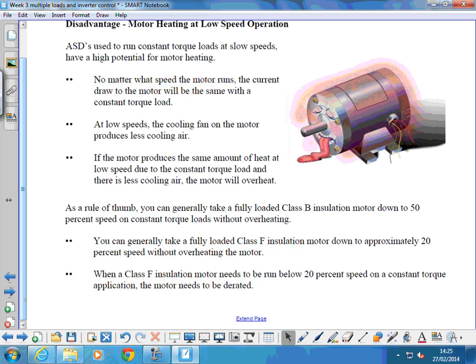If you want to run it any slower than that, you're talking about derating the motor. In other words, you have to install a bigger motor than you normally would to take account of the overheating factor.